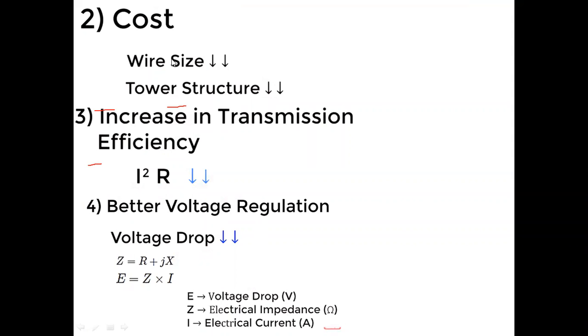Similarly, by reducing the conductor size, the tower structure will also be reduced. To carry 1000 ampere current, the tower structure we will need will also be very high, and a strengthened structure will be required to hold the 1000 ampere current. But now if we step up the voltage, then the current will be reduced, in the previous example, to 22 amperes. So by reducing the conductor size, the tower structure will be reduced, so the cost of the whole system will be reduced this way.